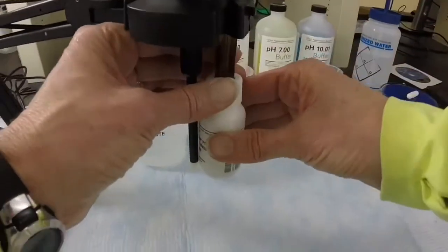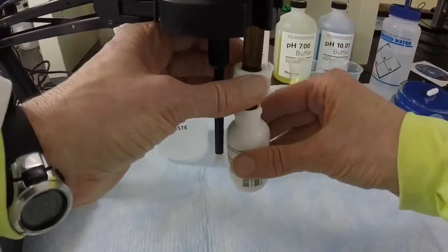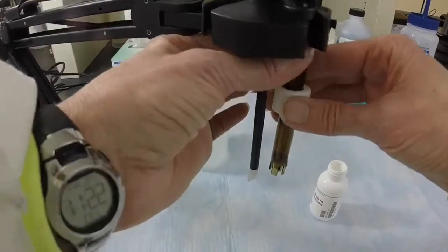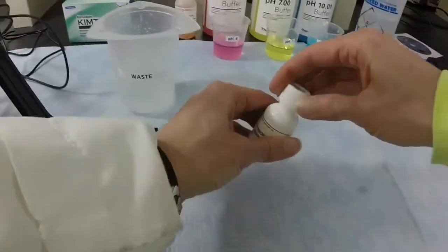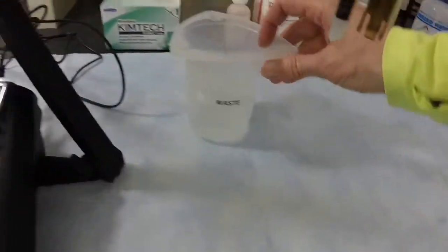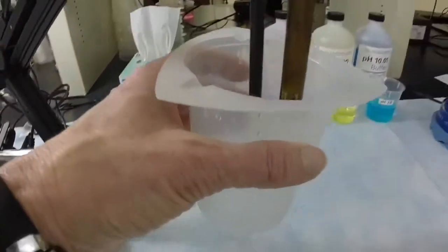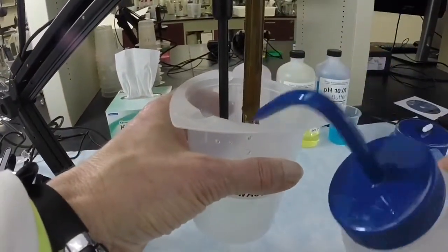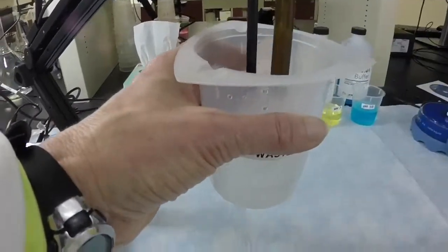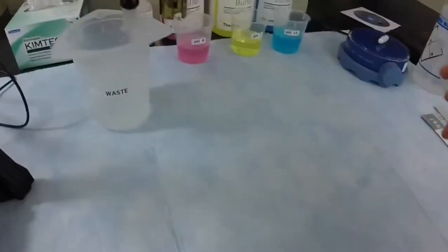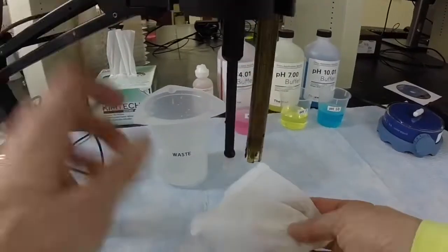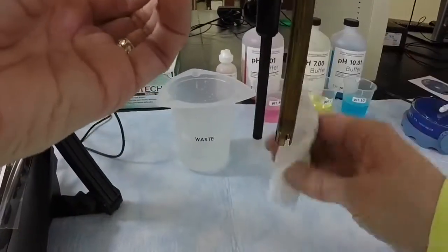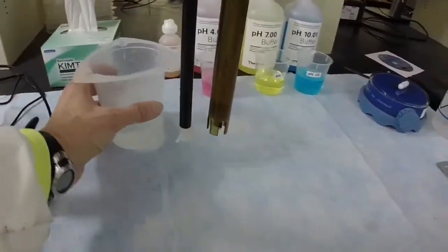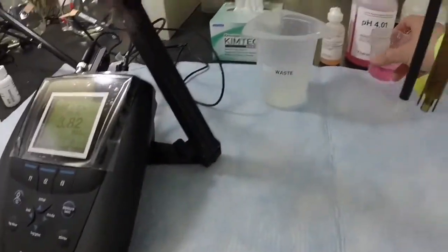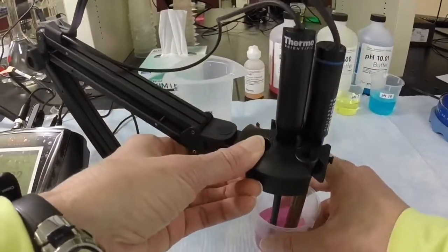To get started, we need to remove the electrode storage bottle from the pH electrode by first unscrewing the top, removing the bottle, and then the cap. Rinse the pH electrode and the mechanical stirrer with DI water from a wash bottle. Then, blot briefly and gently with a laboratory wipe. Put your electrode into the first buffer. In this case, we're starting with pH 4 buffer.